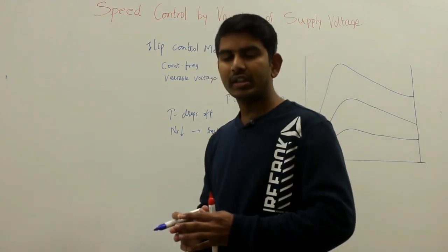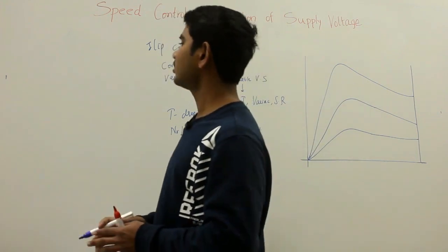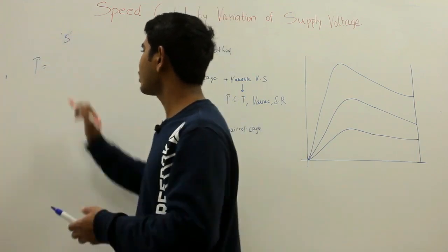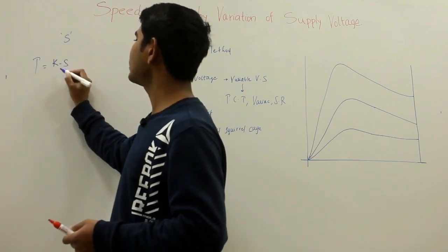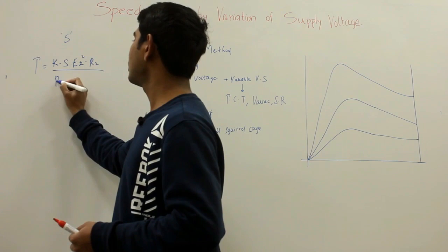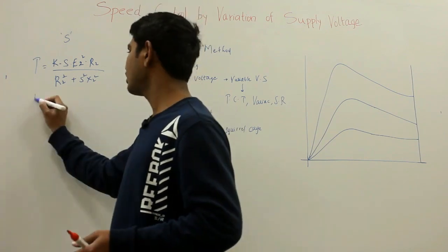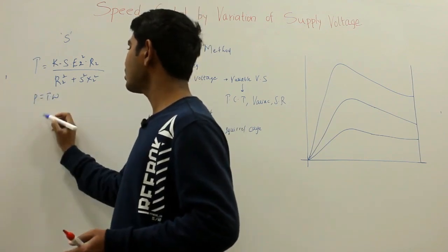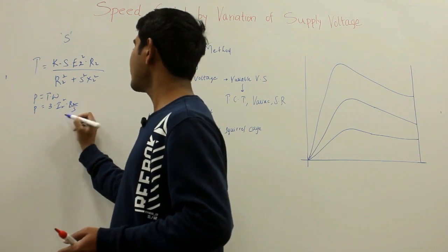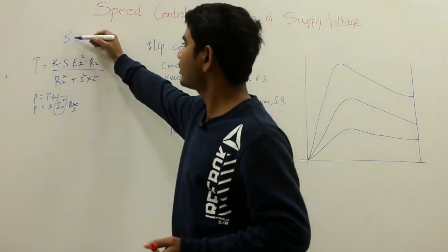Let us consider the torque equation at running conditions for a given slip S. The torque can be given by: T = K · S · E2² · R2 / (R2² + S²·X2²), where K is a constant. This is obtained from power = torque × omega, and power = 3 · I2² · R2/S. By substituting the value of I2, you obtain this torque equation in running condition at a given slip S.